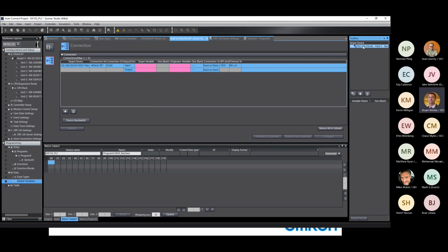I'll double click on that, and that will add it to my connections window. And you can see this is the F430 camera. Now my target variables on my input and output are blank. So what most people like to do is type 1, and that will detect any instance that we have in the EDS file for that device. However, if your instance was below 100, that wouldn't work. So another thing you can do is Control Space, and that will display all of the options for it.